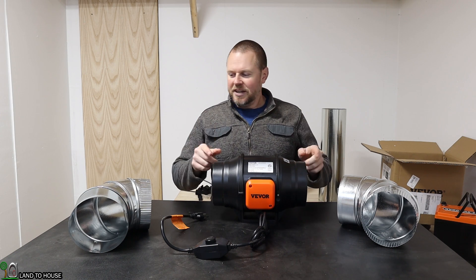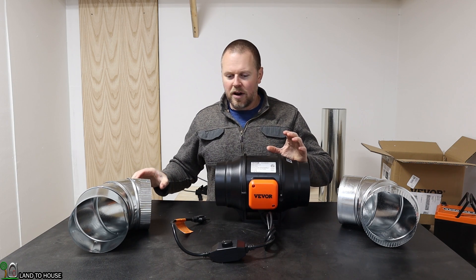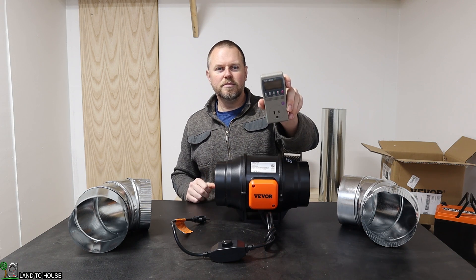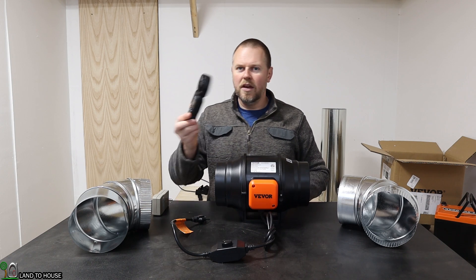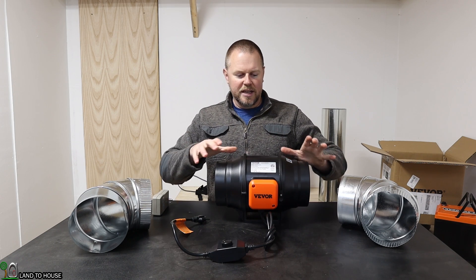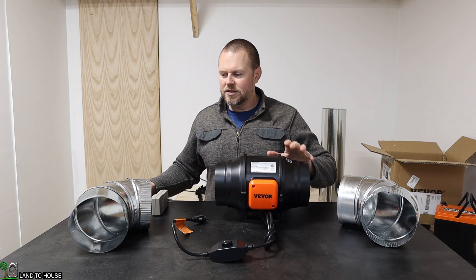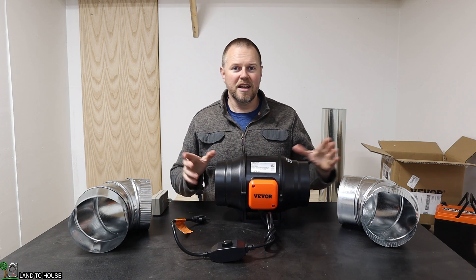I've got my 6-inch ductwork and a VEVOR fan right here. To test out whether a single 90° or two 45s is better, I'm going to do two things: I've got a watt meter, and I'll also be able to see the wind speed using an anemometer. I want to first test the watt value of the fan by itself and get a wind speed, then do a 90° and then 45s to see if there's any difference.